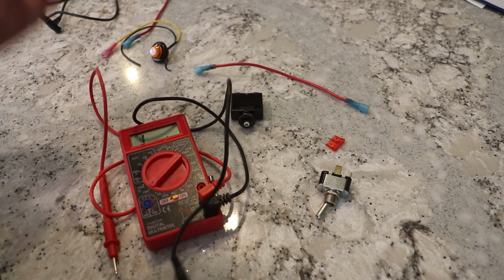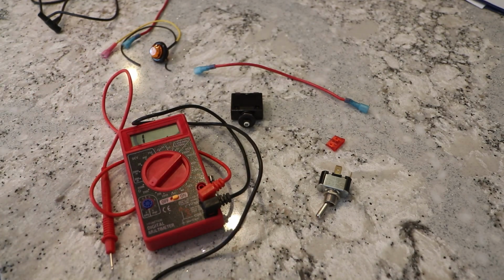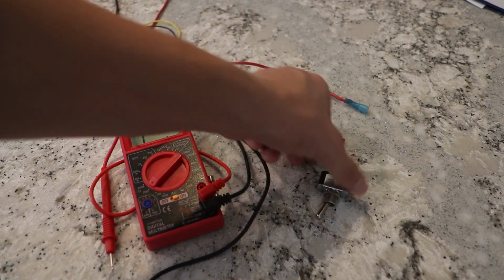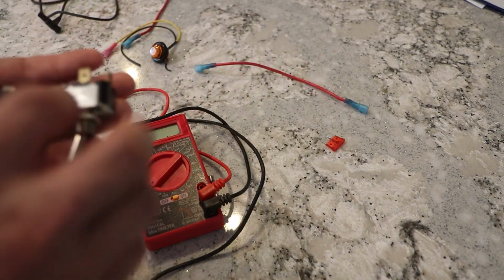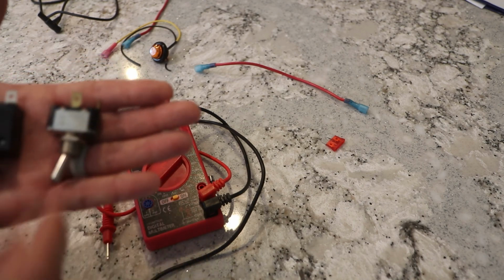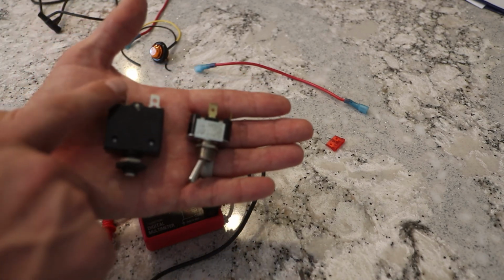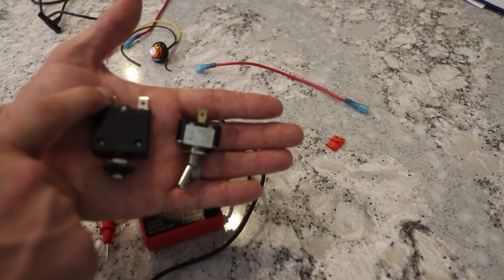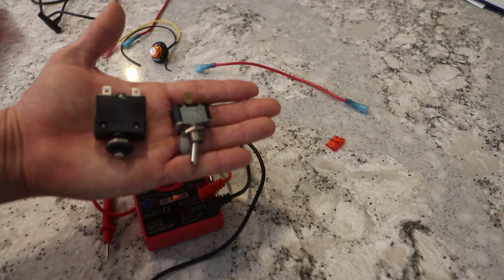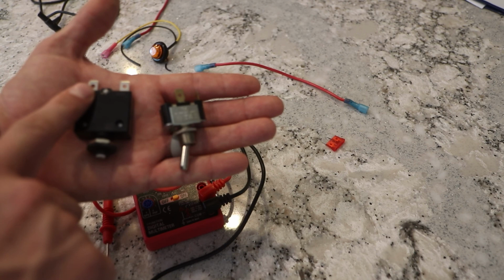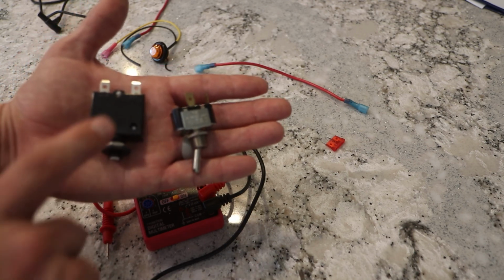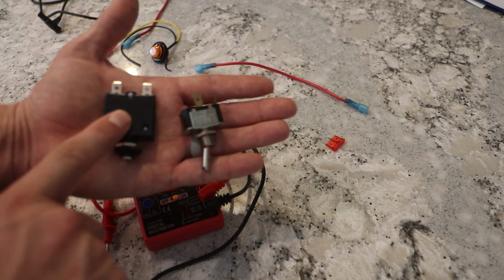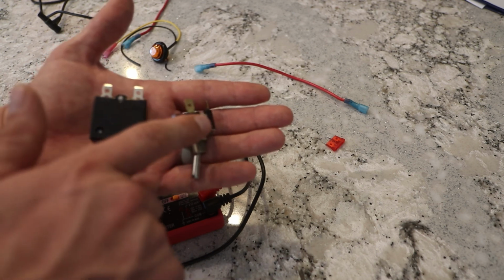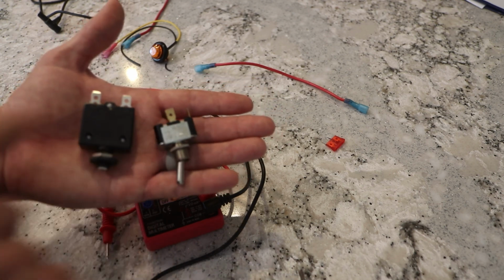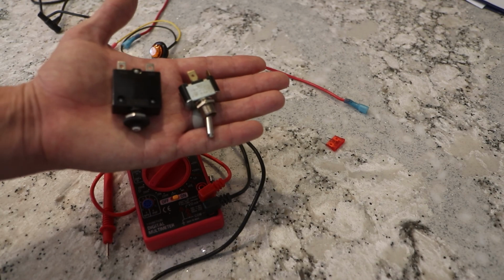Okay, that's about it for troubleshooting literally everything upstream of the battery switch. It's that easy. Quick review: the first thing you always want to test, since it splits the middle and reduces troubleshooting time, is whether you've got voltage coming into the circuit breaker. If you don't, the problem is the battery switch or back. If you do, the only things that could be failing are the circuit breaker or fuse, the wire between each link, the switch, or the device itself, and we've talked through how to troubleshoot all of that.